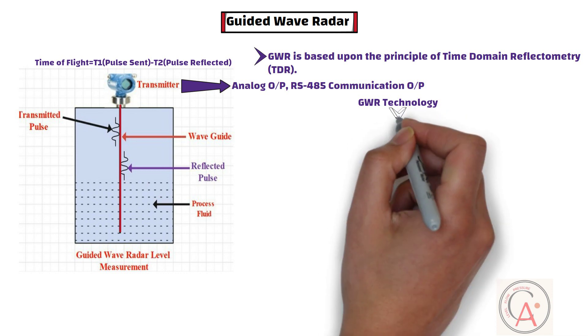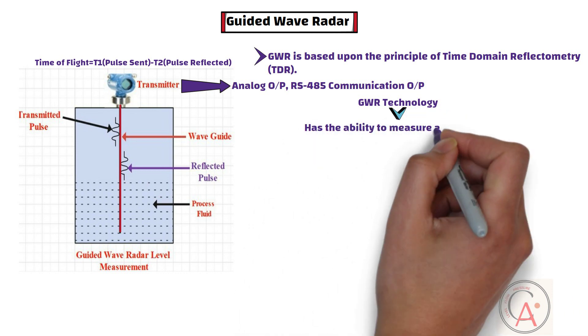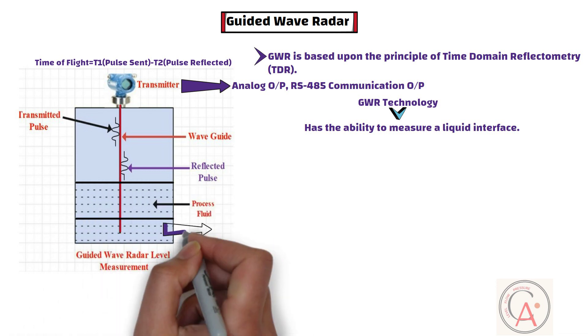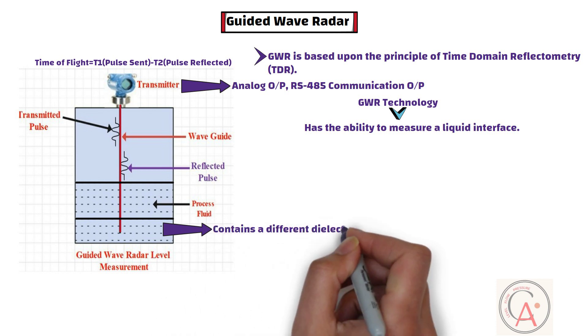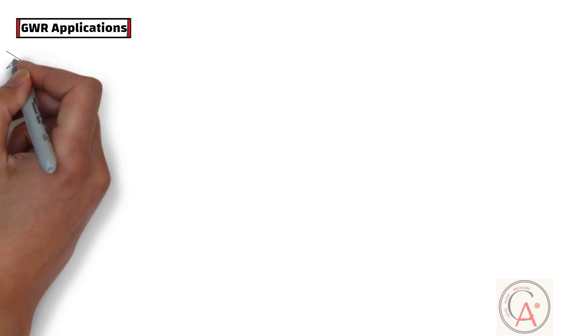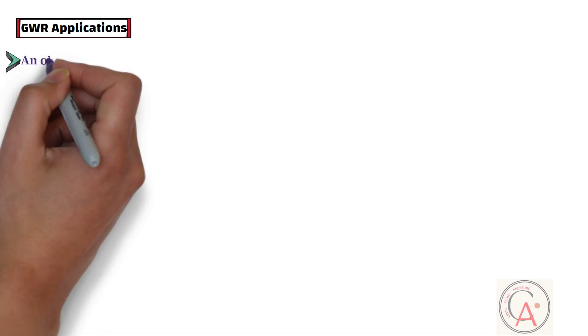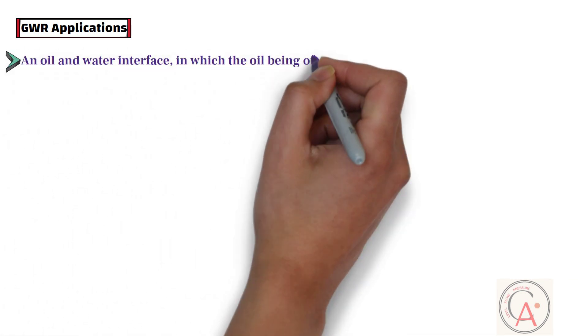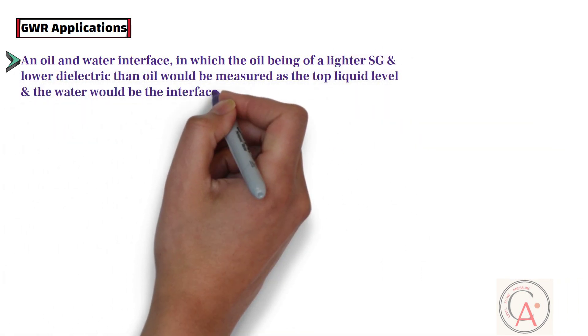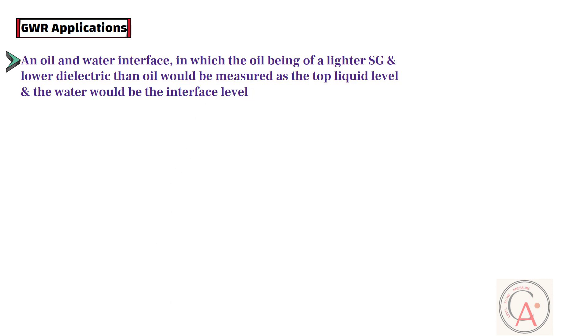Guided wave radar technology also has the ability to measure a liquid interface. A liquid interface is the ability to detect the top liquid level of the media as well as the interface level — the level of the media below the top liquid — which contains a different dielectric or physical property. A typical application would be an oil and water interface, where oil, being of lighter specific gravity and lower dielectric than water, is measured as the top liquid level and water as the interface level.